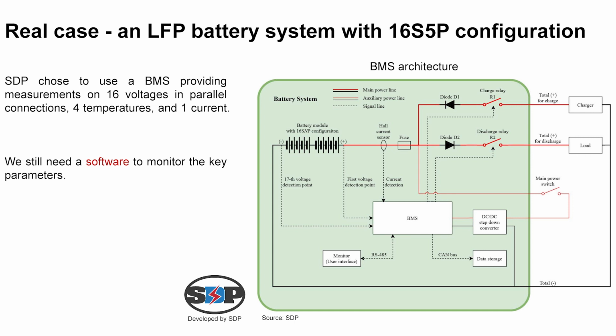The discharge current passes through the discharge relay, R2, the diode, D2, and the fuse. If something goes wrong during discharge, the discharge relay will be turned off immediately by the BMS. The D2 diode guarantees that the current cannot be fed back from the load. The fuse is used on the main power line as a passive overcurrent protection device. It is backup protection when charge and/or discharge relays do not work normally.